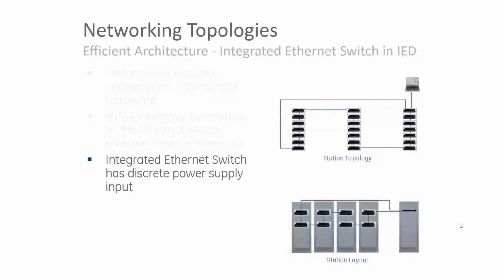And most modern relays do, like our UR relays have standard 3 Ethernet ports. So our 8 series can come with up to 2 Ethernet ports. So most modern devices will give you this architecture. And not only that, it needs to be able to switch in a timely manner. So if there's a break in one of these ring connections, it needs to switch in the other direction. And it needs to do that in a way that's fast and also interoperable if you have multiple different types of devices in that ring.